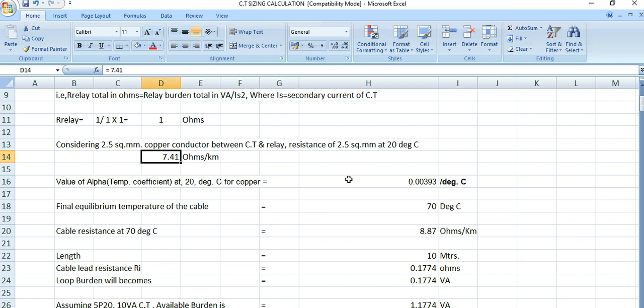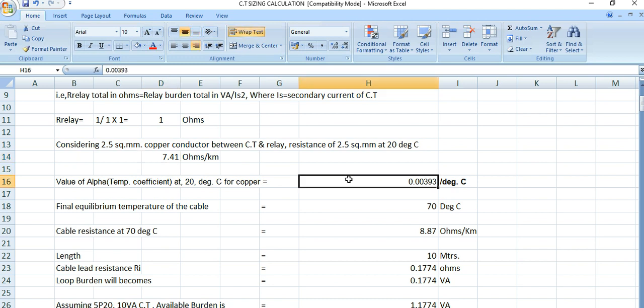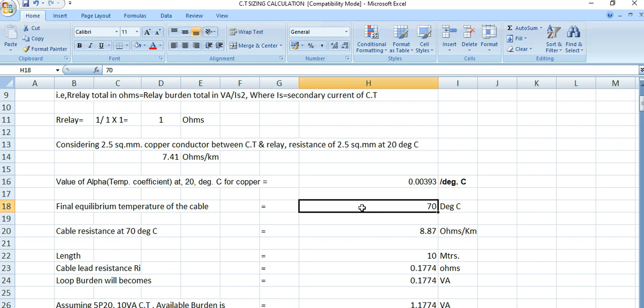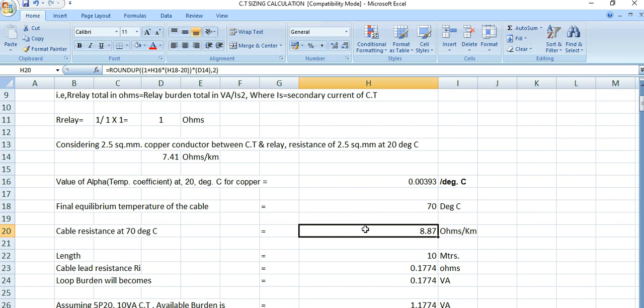The temperature coefficient of copper conductor material at 20°C is 0.00393 per degree centigrade. The final operating temperature for the copper conductor is 70°C, giving a cable resistance at 70°C of 8.87 ohms per kilometer.